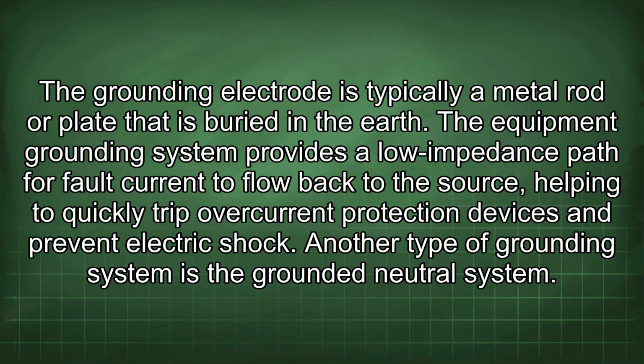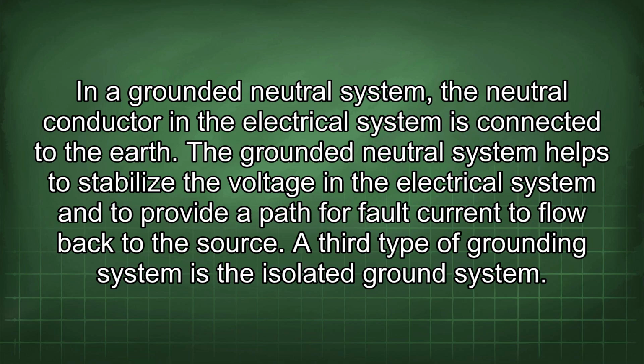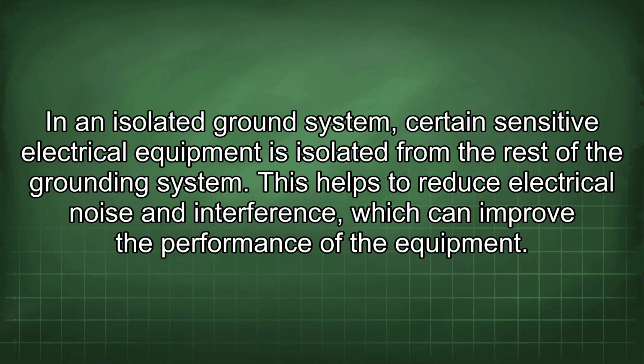Another type of grounding system is the grounded neutral system. In a grounded neutral system, the neutral conductor in the electrical system is connected to the earth. The grounded neutral system helps to stabilize the voltage in the electrical system and to provide a path for fault current to flow back to the source. A third type of grounding system is the isolated ground system. In an isolated ground system, certain sensitive electrical equipment is isolated from the rest of the grounding system. This helps to reduce electrical noise and interference, which can improve the performance of the equipment.